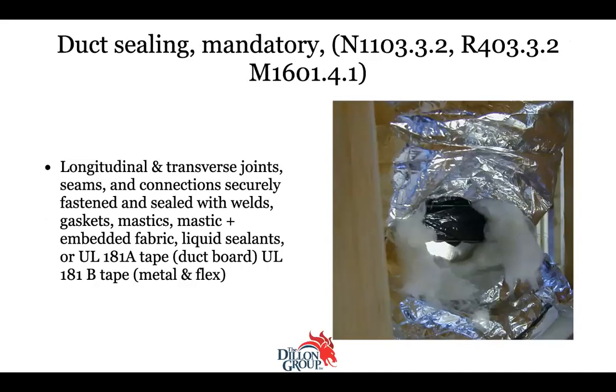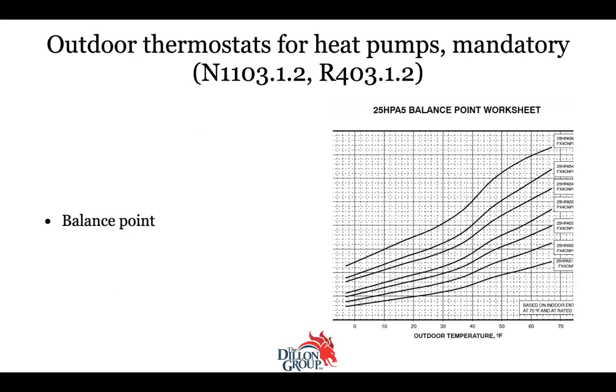Now that's not going to be super simple for an inspector to check, that the balance point was set correctly. I mean, you're removing panels and getting to a thermostat, or is it fairly easy? It's a little more complicated, but what I just say is, can you show me your balance point worksheet? There you go. Because at least then I can see, did they at least do that? That's great. If they didn't do that, then you know they didn't do it. Yeah, and that should be required.